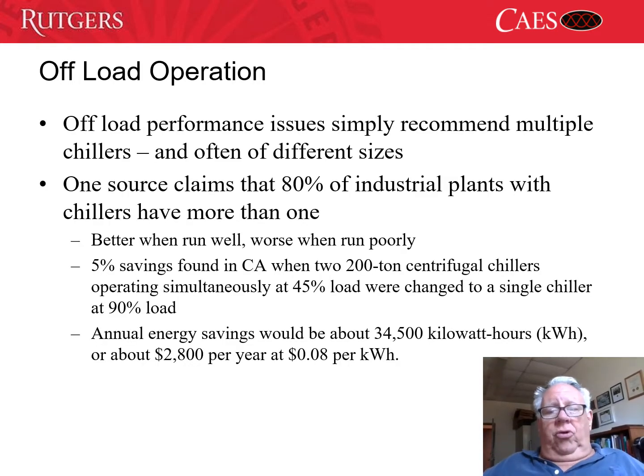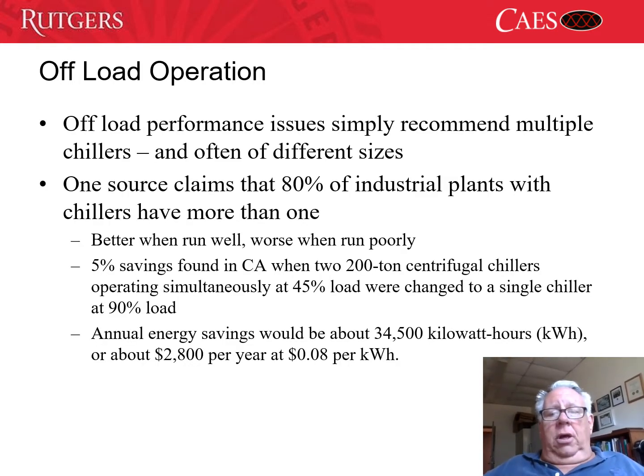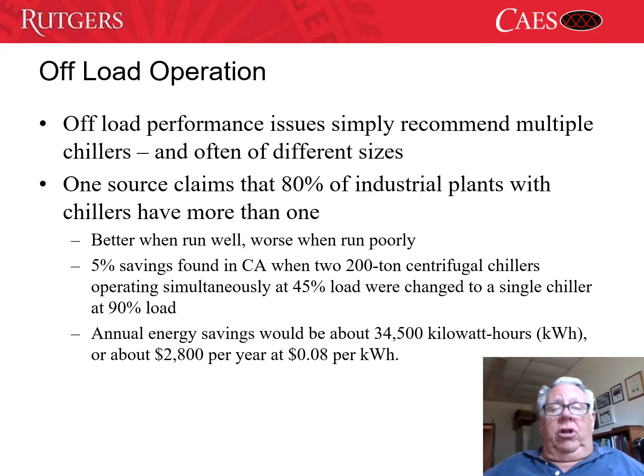So this sort of off-load performance brings up the idea of having multiple chillers and, quite honestly, having them in different sizes. Okay, I saw one source that said 80% of industrial plants with chillers have more than one chiller. Well, this is the good news. The bad news is if you don't run them correctly, you may not be helping anything.